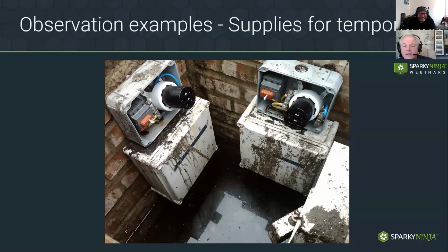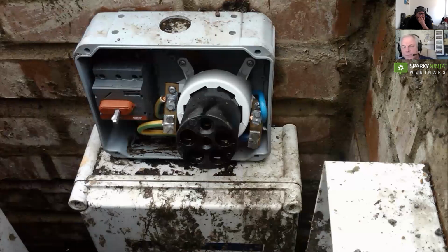Good observation. So the issue here is, as I say, a firm had been in and said these are okay, no damage, they just need a bit of a clean and a dry. We came in prior to an event when I was testing the circuit to see what the supply was to the marquee, and we got an earth loop impedance of 65 ohms on this one. The other one was still okay.